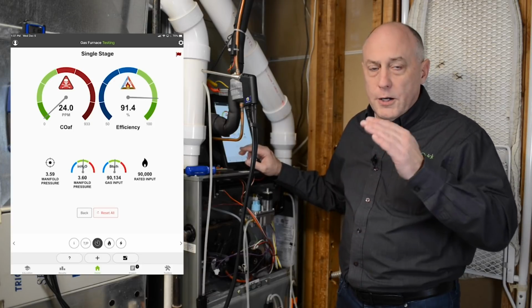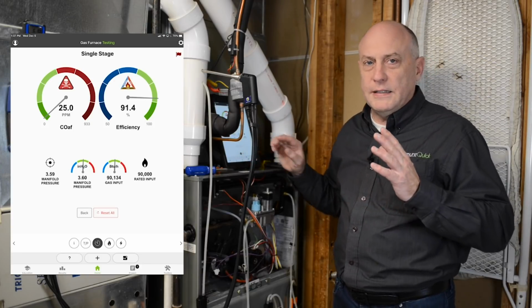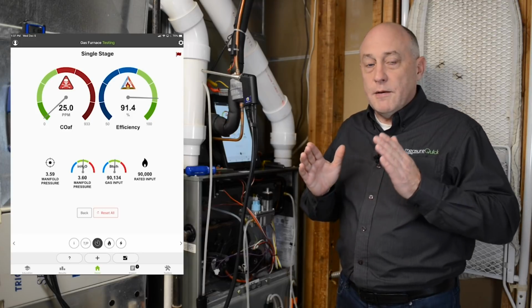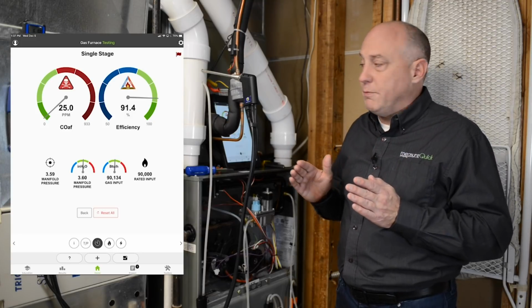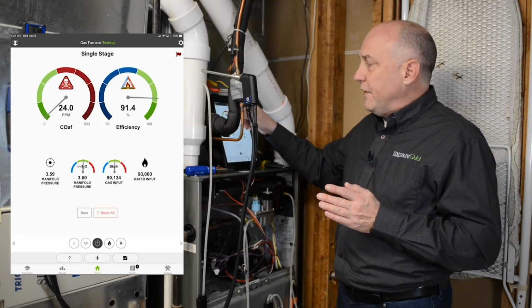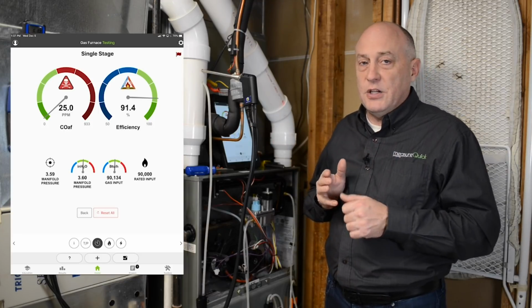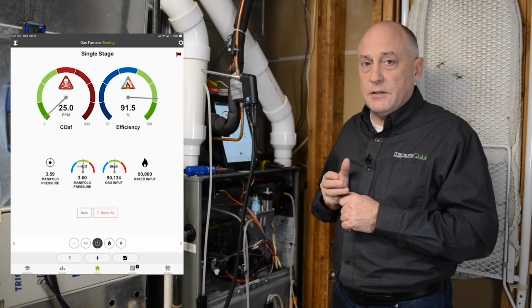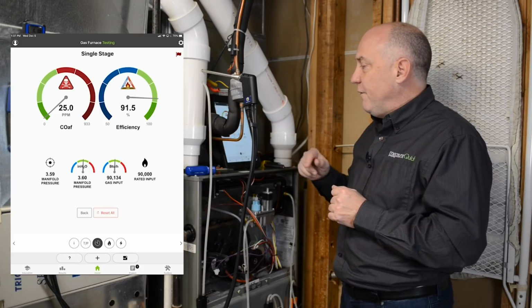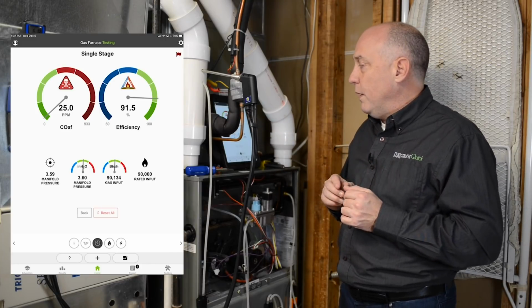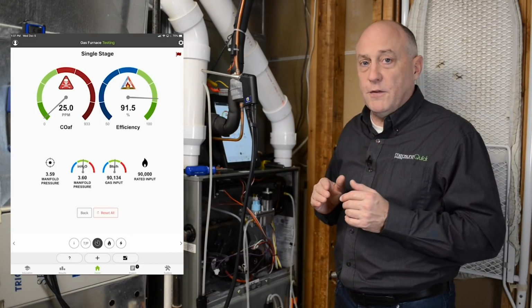Anything below 100 parts per million we consider an industry standard acceptable. The maximum allowable is 400 parts per million. So when that gets off that green section into the red section of the gauge, your CO is way too high and you need to do something with that appliance. You can see my efficiency is running around 91.5%, which, again, is good for this appliance.